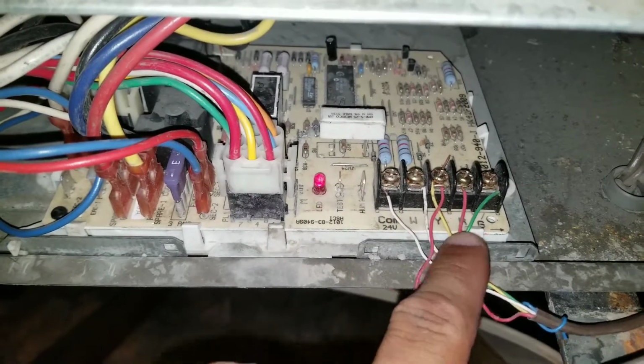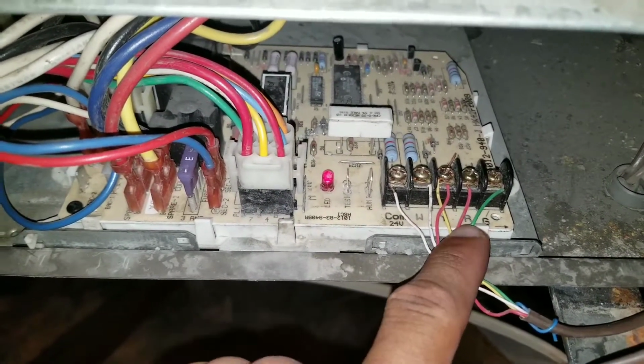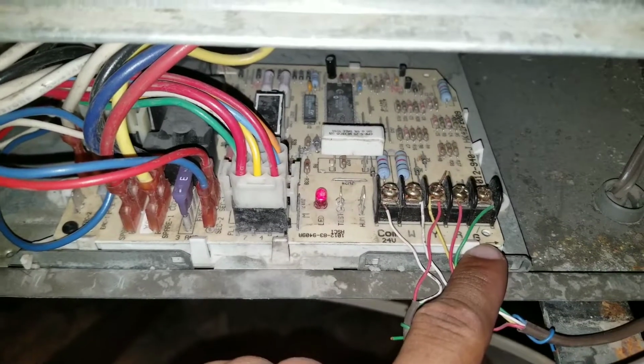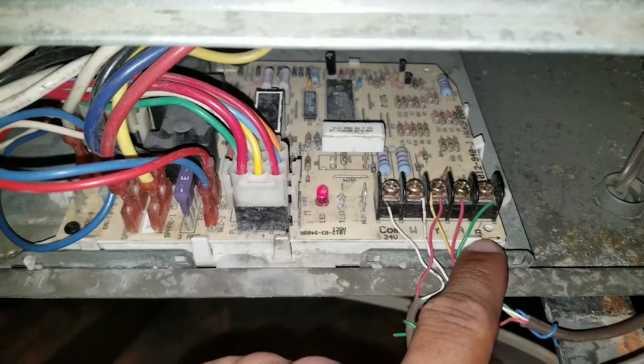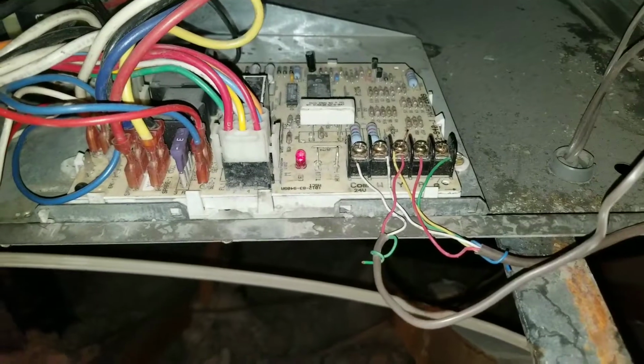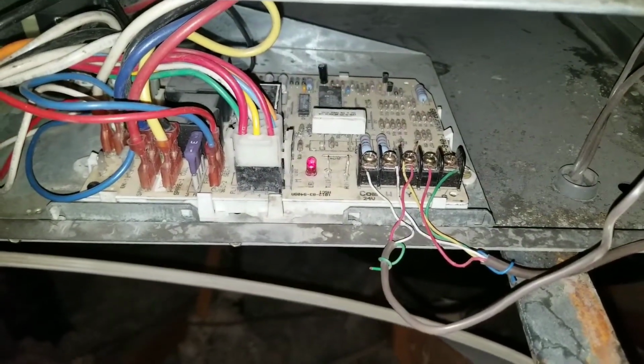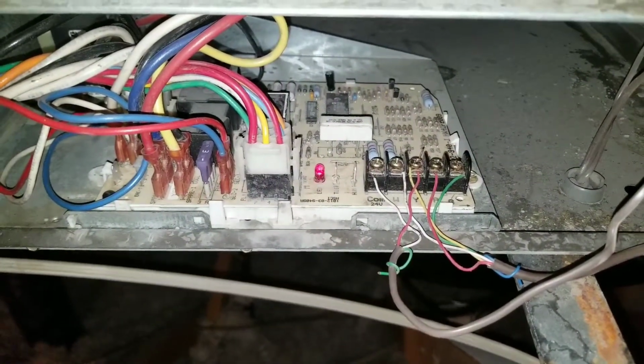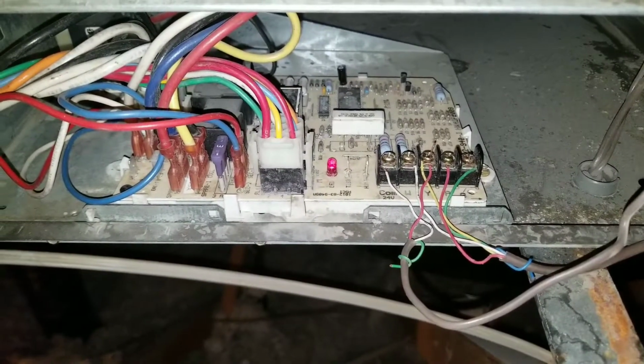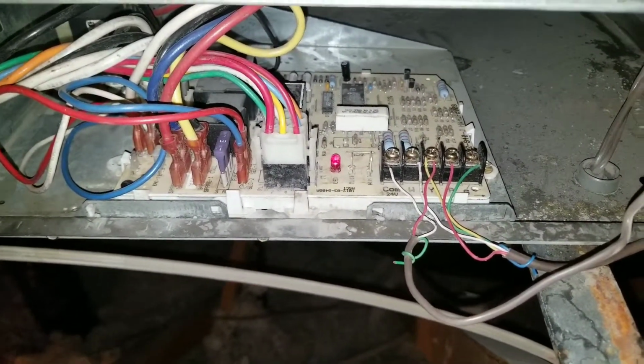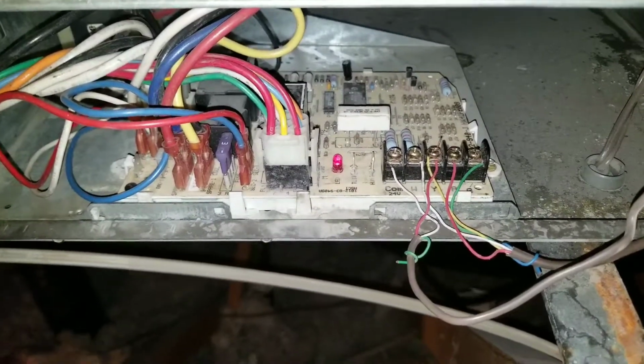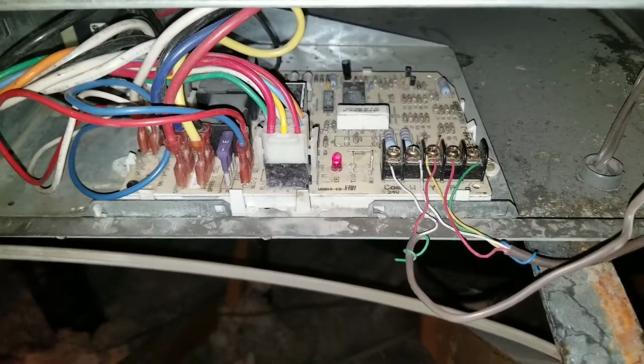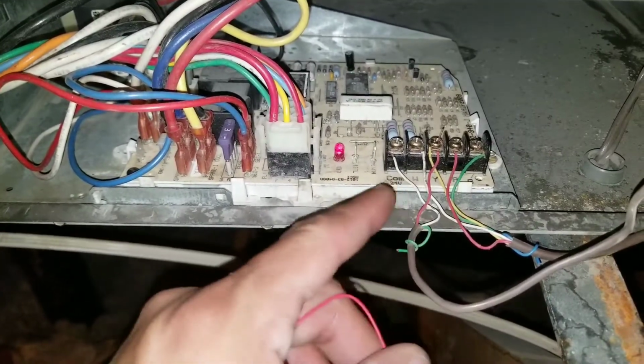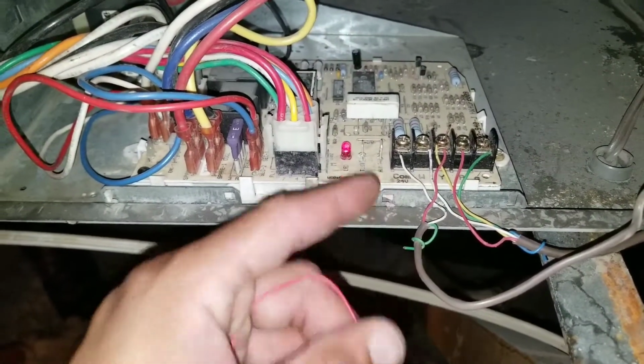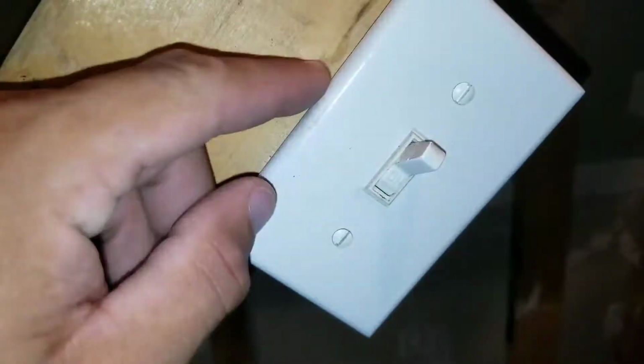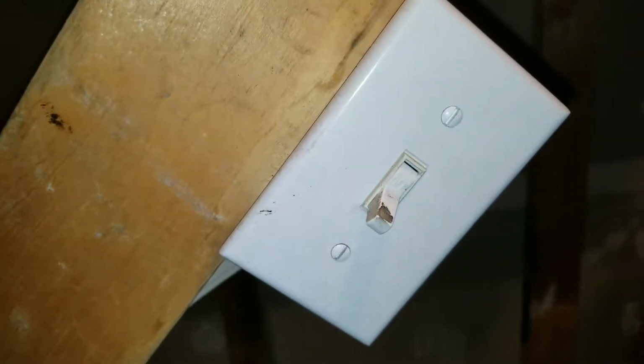Here we have our R, that's going to be our 24 volts. And here we have our G terminal. The G is going to be your blower motor. Let's say right now I received a call, I inspect the system, and I see that my blower motor is not running. The first thing we're going to want to do is inspect the system. So instead of going downstairs and turning the thermostat to the on position, I'm going to jumper it out here, and this will allow me to troubleshoot without having to go back and forth. I'm going to turn my incoming power off.